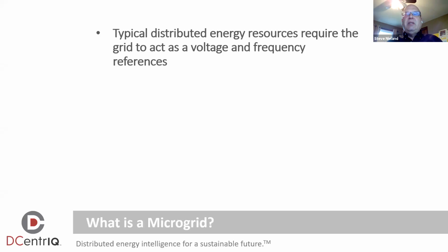Well, that's where we need to look at the difference between those distributed generation capabilities and a microgrid. So what's different about a microgrid? Typically, those distributed energy resources require the grid to act as a voltage and frequency reference. Something has to tell me what 120 volts is and what 60 hertz is, or what 480 volts and 60 hertz is. Without the grid, there's nothing there to act as a reference. I need something else to take the place of the grid to do that.